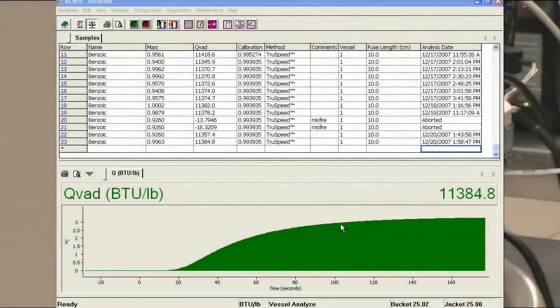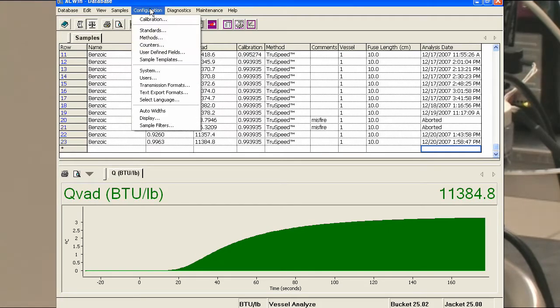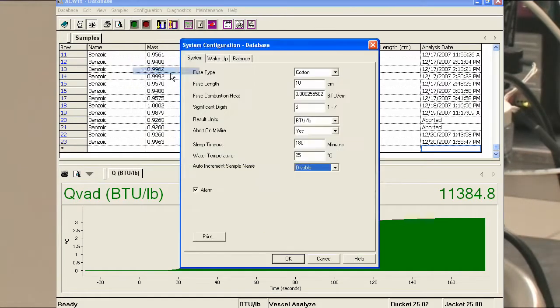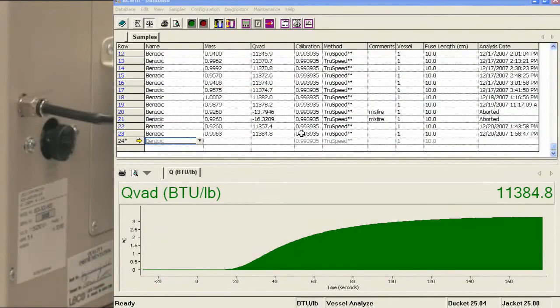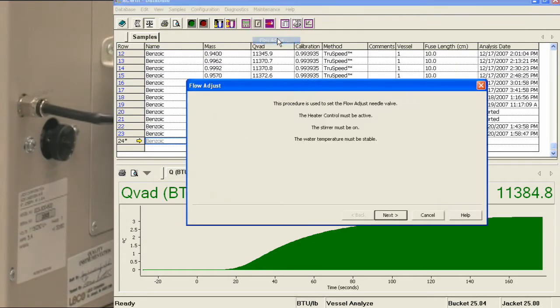After the system is stabilized some, you want to go into the system page under configuration and set the temperature. The water temperature should be set 3 to 4 degrees above the ambient temperature. You will have to allow the instrument, once again, to stabilize out some, and then you can set the duty cycle. To set the duty cycle, you have to go into the maintenance tab, and you will see a flow adjustment. You'll let that screen come up.